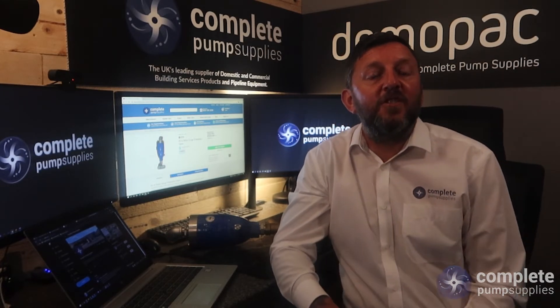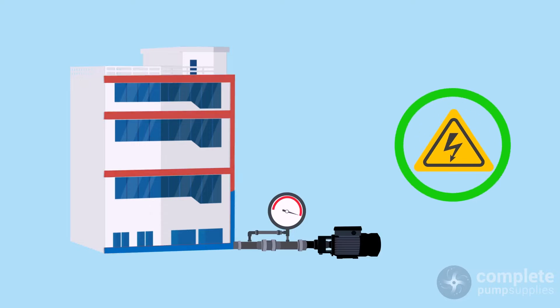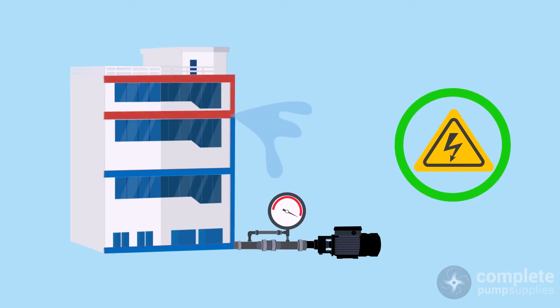When the power is restored and the pump begins to operate again, restoring system pressure to preset levels, the worst case is that the pressurized water is pushed into a vacuum and the water will accelerate beyond the expected design velocities. This will cause a hydraulic shock to the pipework, potentially beyond the test pressure of the system. These high pressures can cause weak pipework or connections to burst, causing potentially serious flooding and expensive water damage within the building.